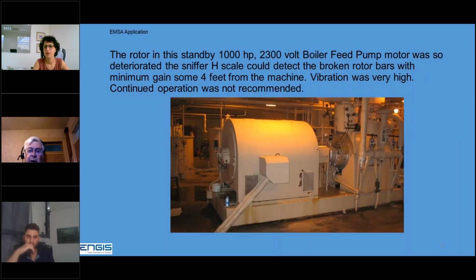This old motor was at a plant down in Texas, 2300 volts. The H scale is the magnetic field scale on the sniffer, very insensitive, and this had so many broken rotor bars in it that we could measure it well over a meter from the motor, full scale with minimum gain. So continued operation was not recommended.